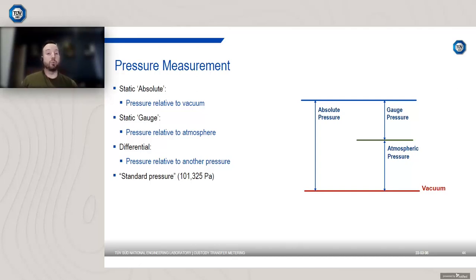Differential pressure is simply pressure relative to another pressure. This is quite critical for things like orifice plates and venturi tubes. And we talked about standard pressure. Again, this is key for converting to things like gross standard volume, for example. Typically it's 1.01325 bar, but it's not a given. You need to make sure that whenever standard pressure is used for converting quantities, it's stated somewhere what the standard conditions are.